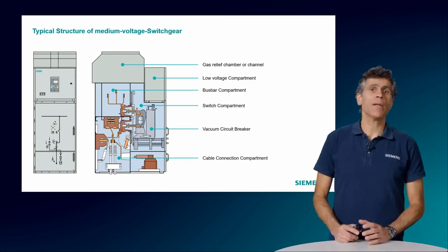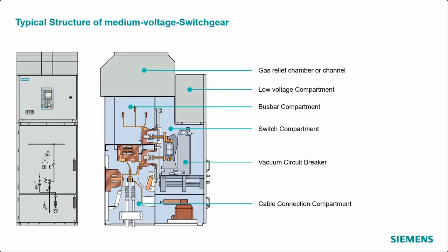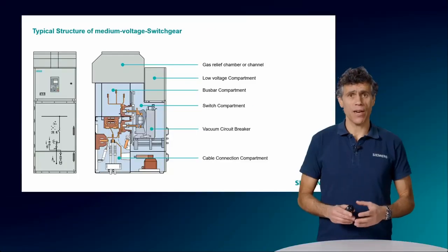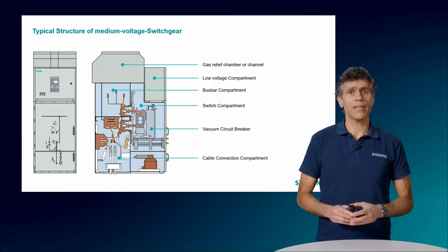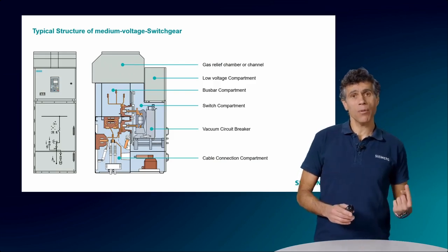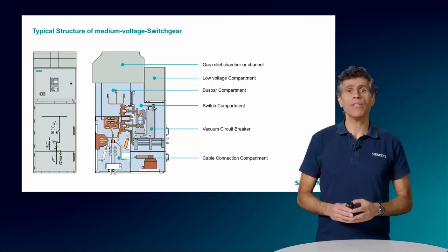In a feeder panel, which is a panel connected to something that consumes energy, the current flows from the busbar to the cable compartment. It comes from the busbar, it flows through the breaker, which can open or close its contacts. When the contacts are closed, it flows into the connection compartment into the cables. On this path, you may see that some devices are placed. We will see later which devices are those and what their functions are. In an incomer, the current flows the other way around, from the cable compartment to the busbar. But mostly you have the basics done now.